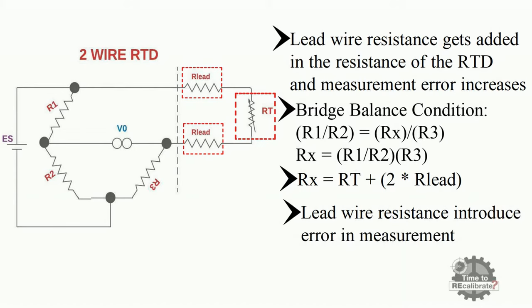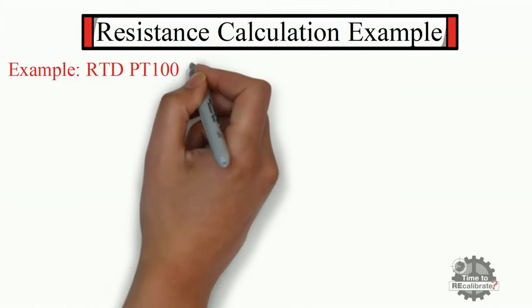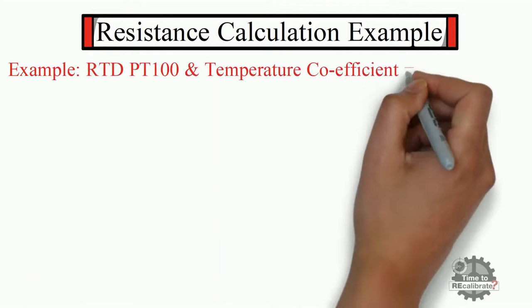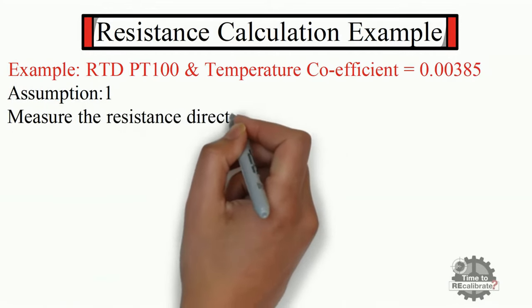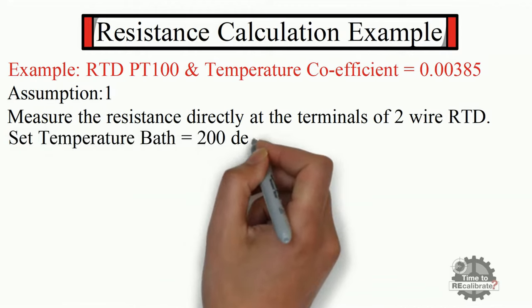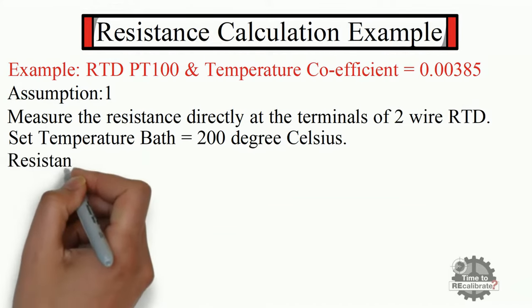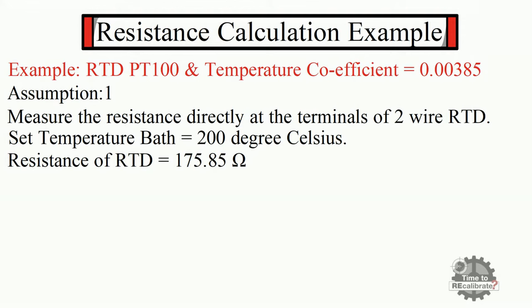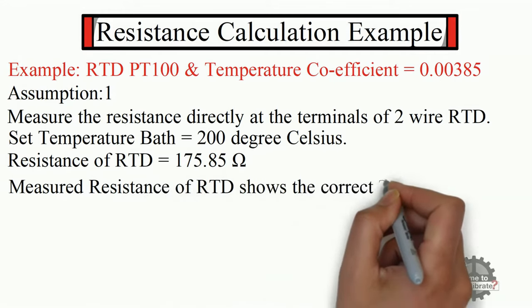Let's understand this with two examples. We have taken RTD PT100, and the temperature coefficient of this RTD is 0.00385. Assume we are measuring resistance directly at the terminals of the 2-wire RTD — in other words, without any lead wires. Put the RTD in a temperature bath and set the temperature to 200 degrees Celsius. Measuring the resistance at its terminals, you should get 175.85 ohms, which is the correct measurement — the measured resistance shows the correct temperature reading.